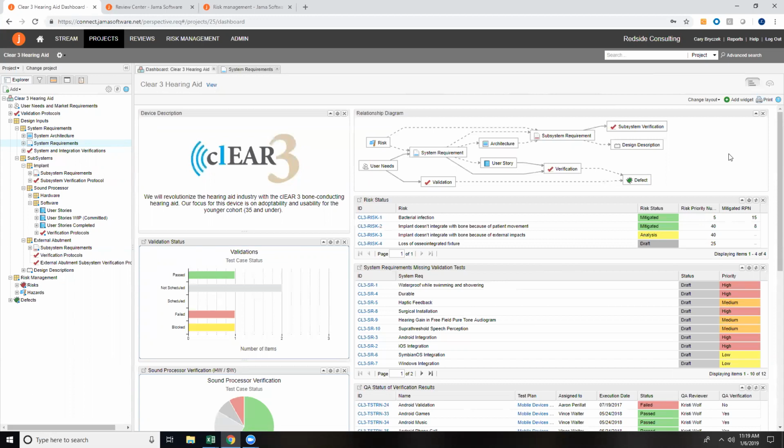It sets the stage for the information that I'm collecting in my project. This set of rules very much follows 21 CFR 820 and relative parts of ISO 13485. Jama prevents you from making traces outside of this set of rules, so you don't want to introduce risk by allowing inappropriate traces between your data.